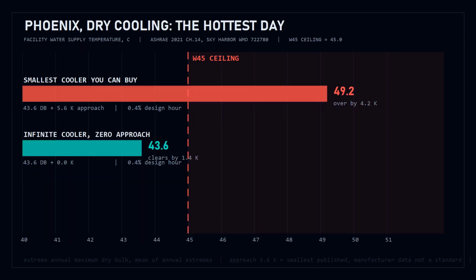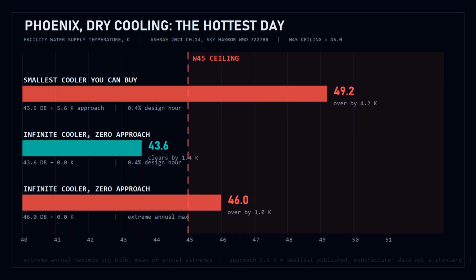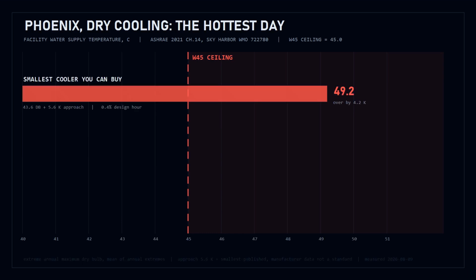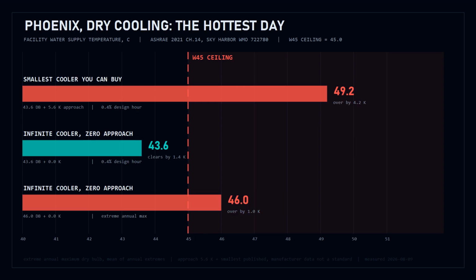ASHRAE also publishes the extreme annual maximum. And for Phoenix, that is 46.0 degrees. The infinitely large cooler, the one that does not exist, the one with zero approach, delivers 46-degree water on the hottest day of an ordinary year. It misses W45 by a full Kelvin, not the catalog, the air. On that day, the wall is real, and no cooler you can buy or imagine gets over it.